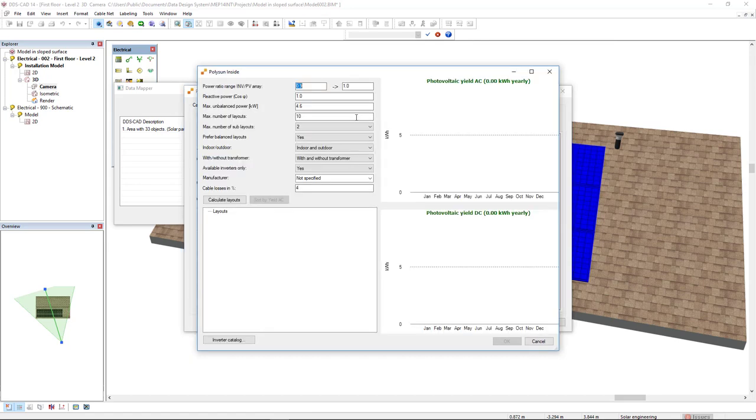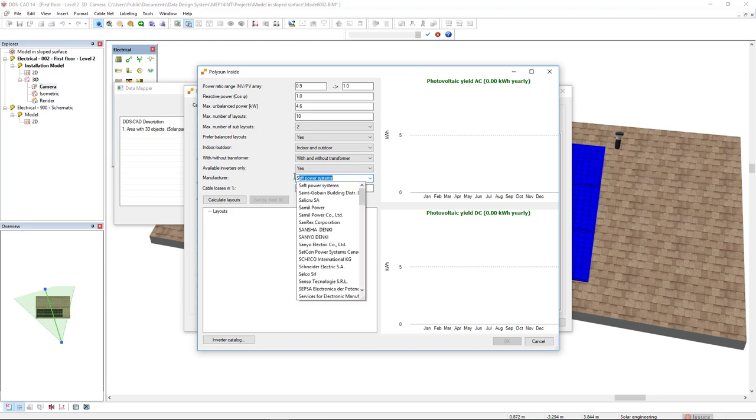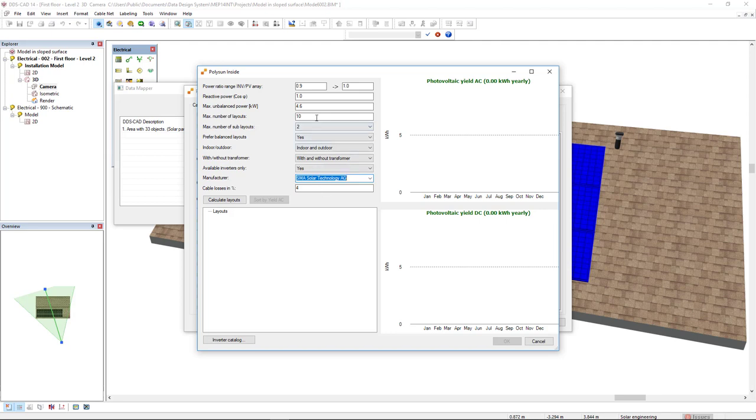Having set this information, I will search for a suitable inverter by clicking on Find suitable inverter option. These filters will help you to find a suitable inverter. In this case, in the manufacturer field, I will type SMA Solar Technology AG. Important here as well is that I will set the maximum number of layouts as 10 and the maximum number of sublayouts as 2. And I will click calculate layouts.